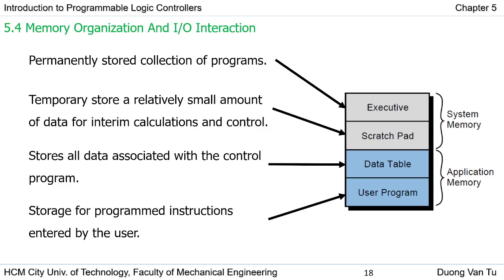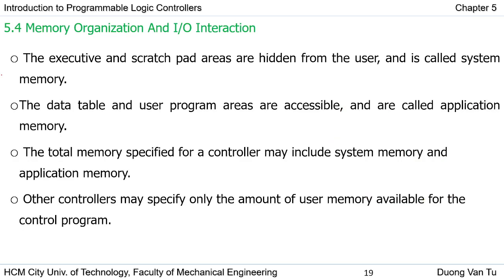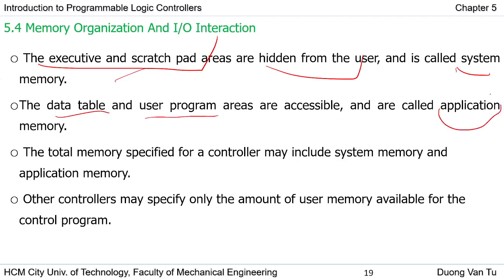Now we can see the memory organization and I/O interaction. The overall memory in the PLC contains the system memory and application memory, divided into four areas: executive, scratch, data table, and user program. The user program stores the control program prepared by the programmer, and the data table contains user data. The executive and scratch areas are hidden from the user, used by the manufacturer — these form the system memory. The data table and user program are accessible to the user and form the application memory.